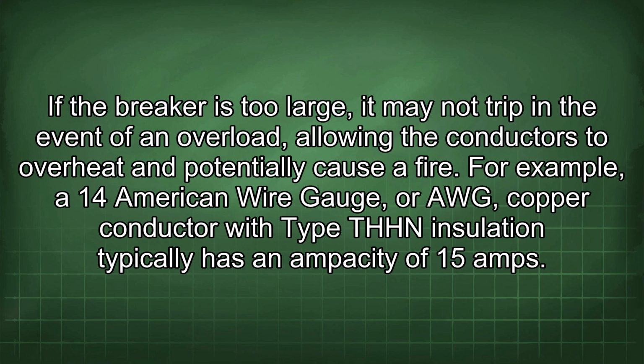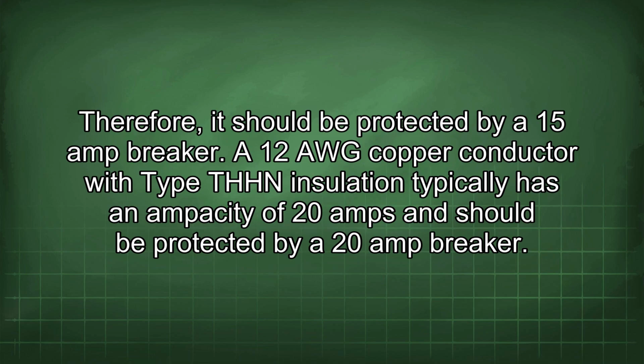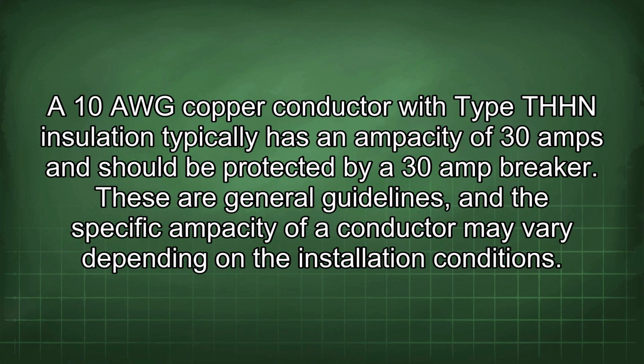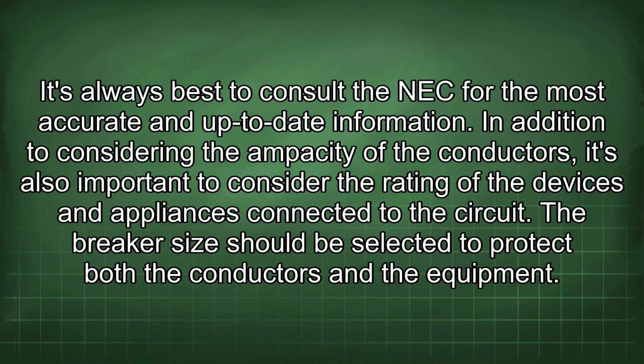For example, a 14 American wire gauge, or AWG, copper conductor with type THHN insulation typically has an ampacity of 15 amps. Therefore, it should be protected by a 15 amp breaker. A 12 AWG copper conductor with type THHN insulation typically has an ampacity of 20 amps and should be protected by a 20 amp breaker. A 10 AWG copper conductor with type THHN insulation typically has an ampacity of 30 amps and should be protected by a 30 amp breaker. These are general guidelines, and the specific ampacity of a conductor may vary depending on the installation conditions. It's always best to consult the NEC for the most accurate and up-to-date information.